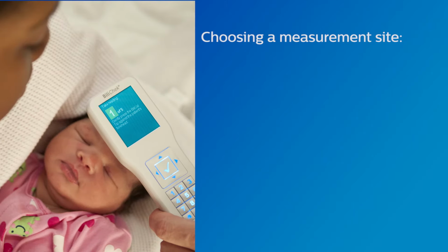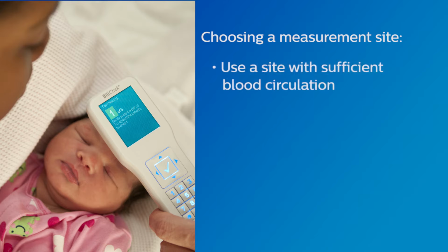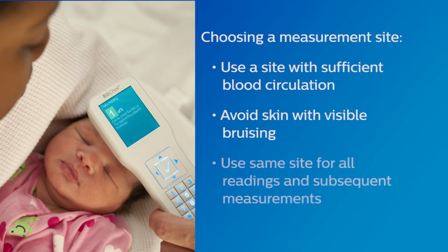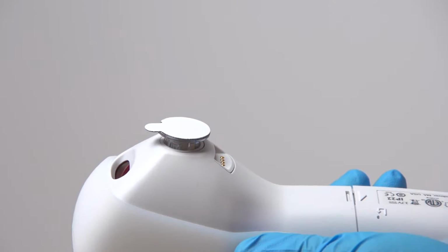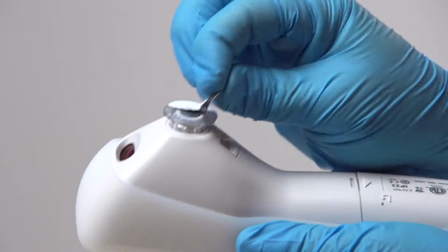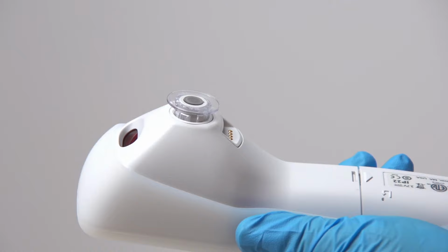Choose an appropriate measurement site. Use either the flat area of the forehead between the infant's eyebrows or the sternum, where a sufficient amount of blood is circulated. Avoid areas of the skin with visible bruising. The same site should be used for all readings during a measurement, and the same site should be used for all subsequent measurements.